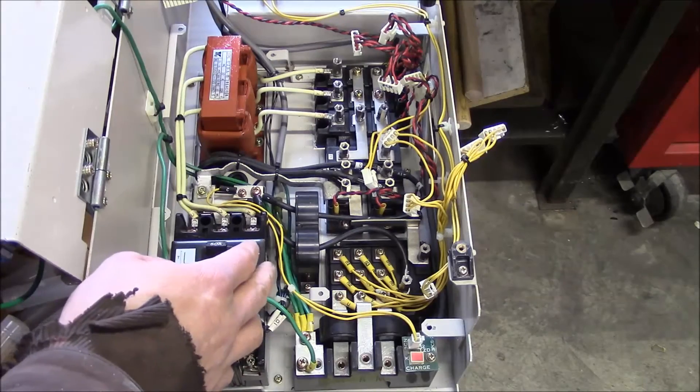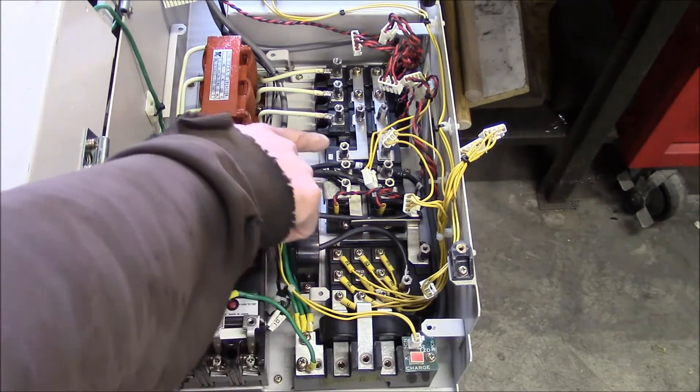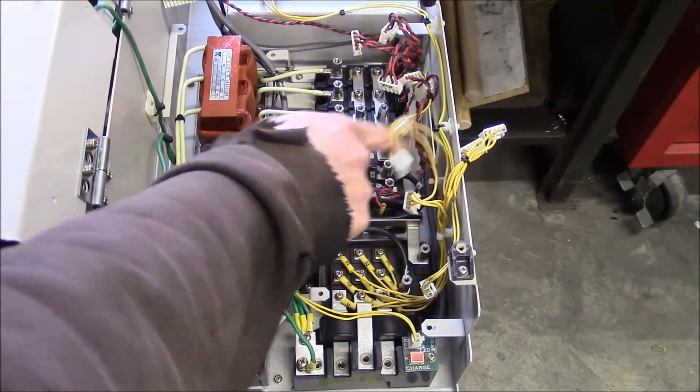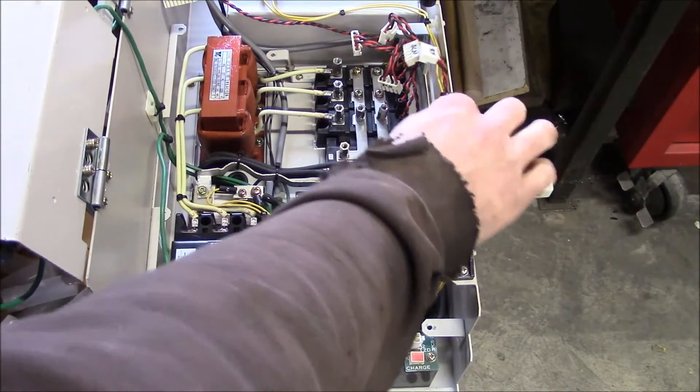With the problem on the braking circuit, we can pretty well narrow it down to these IGBTs here that are controlling the braking.